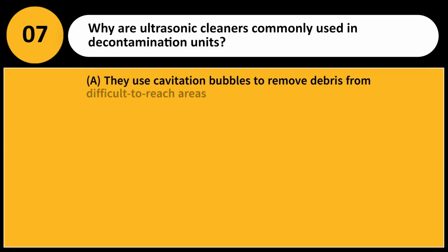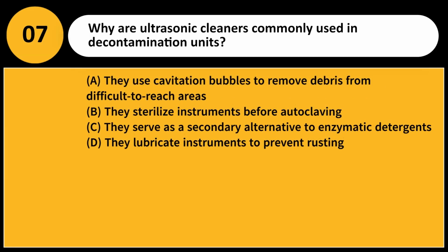Why are ultrasonic cleaners commonly used in decontamination units? A. They use cavitation bubbles to remove debris from difficult-to-reach areas. B. They sterilize instruments before autoclaving. C. They serve as a secondary alternative to enzymatic detergents. D. They lubricate instruments to prevent rusting. Answer, A.